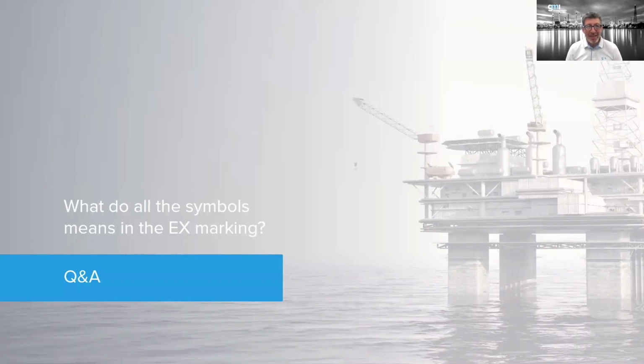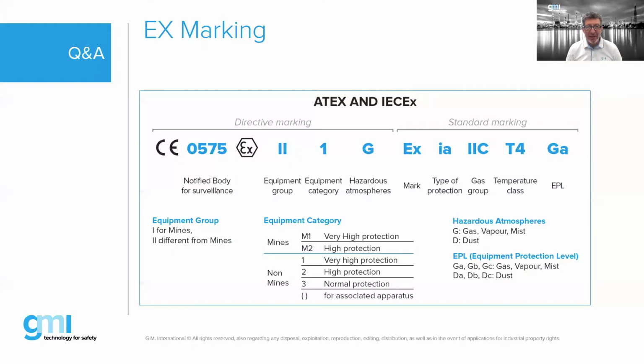What do all the symbols mean in the EX marking? So we have a lot of markings, and you talked a little bit earlier about the marking. I'll go through this briefly, and it can be confusing. What you see is the directive marking information on the left-hand side. The CE is telling you that it's compliant to one or more European directives. Now, if you see a CE mark on a product and you don't see the EX in a hexagon, that means it's compliant to possibly another European directive, not necessarily the ATEX directive.